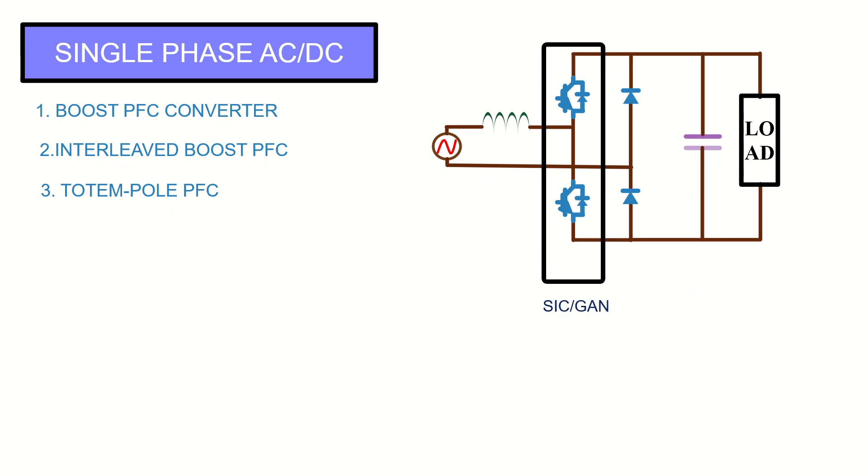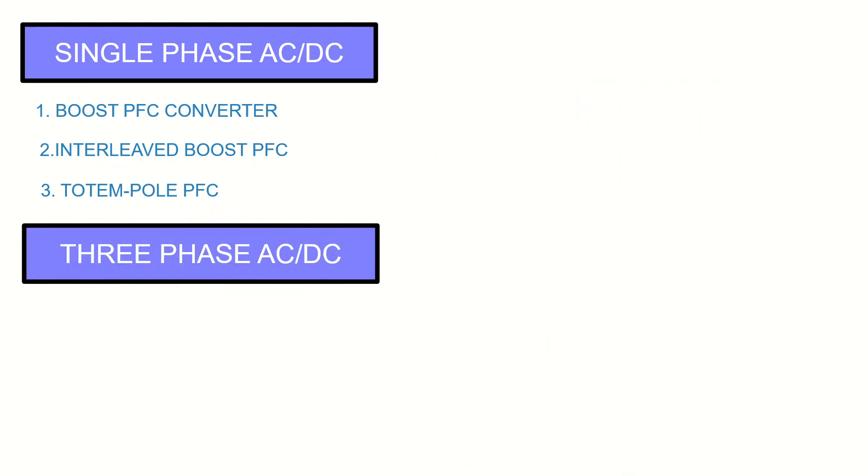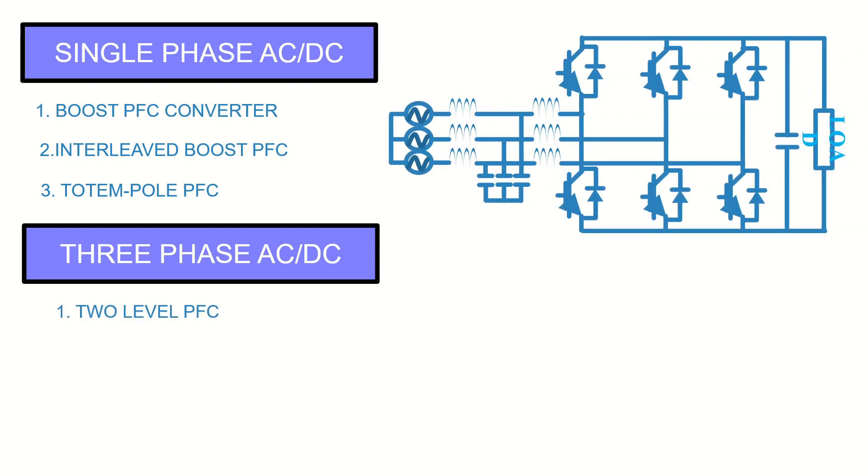In the high-frequency leg of totem pole PFC, silicon carbide or gallium nitride devices are used. And in the low-frequency leg, diodes or silicon MOSFETs are used. For three-phase operation, most common topology is two-level PFC converter. Two-level PFC is a six-switch boost type rectifier, features a very simple circuit topology and easy control. It has bi-directional power flow capability and can achieve a high power factor with reasonable efficiency. One of the drawbacks of this topology is the bulky filter inductor, which it requires to regulate the input current THD to low values.